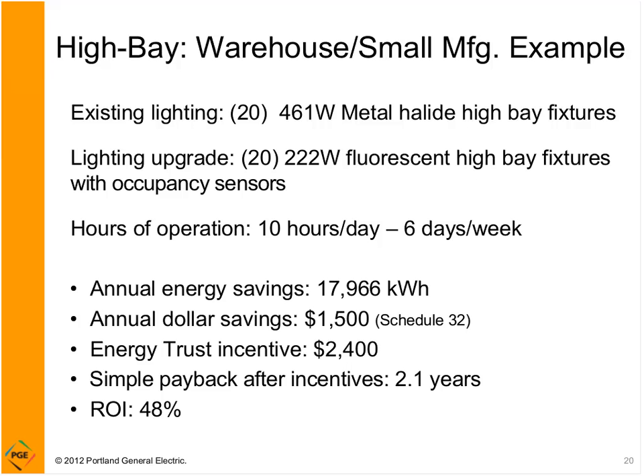This is assuming annual hours of operation of 10 hours a day, 6 days a week. The annual energy savings is expected to be almost 18,000 kilowatt hours. Annual dollar savings, about $1,500. Energy Trust incentive, about $2,400, resulting in a simple payback after incentives of 2.1 years, or a return on investment of 48%. So it looks like a really good project.